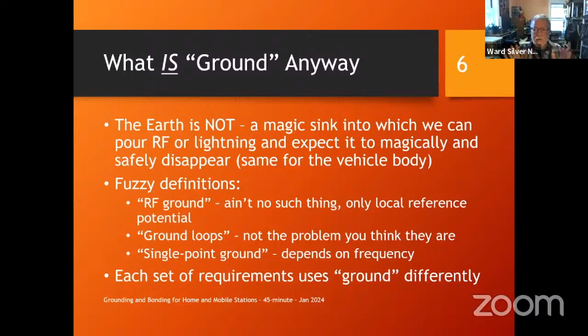So something can be the size of a football stadium and still be pretty electrically small. But at 20 meters or 6 meters or whatever, electrically small is drastically smaller. And so you have to be careful about throwing the words single point ground around. Each set of requirements that you encounter, the AC, the lightning, the RF, they use ground differently. You've got to be careful about how you use them. Okay, bonding. We're all bonding here.